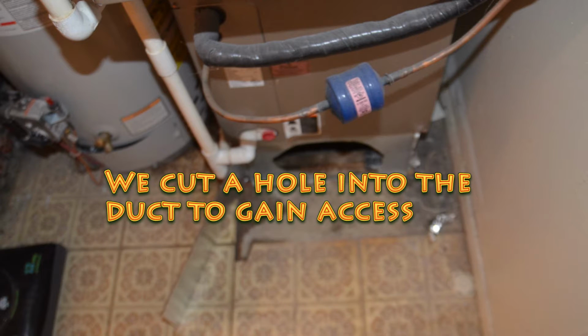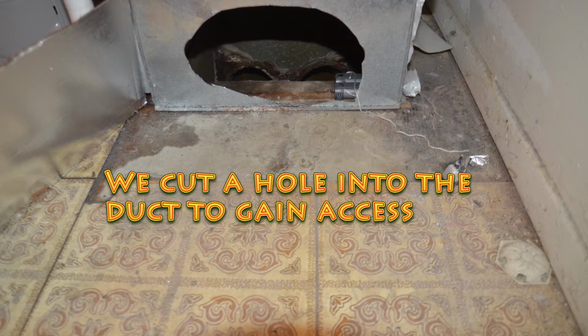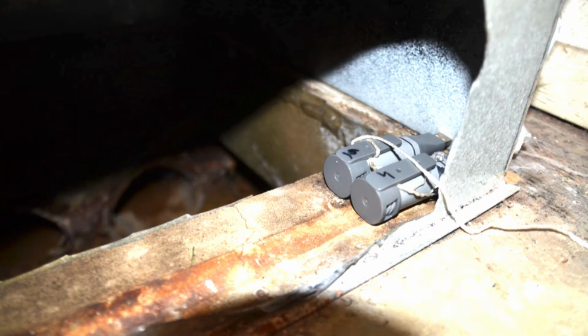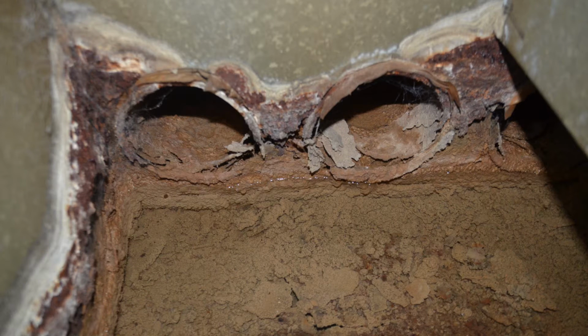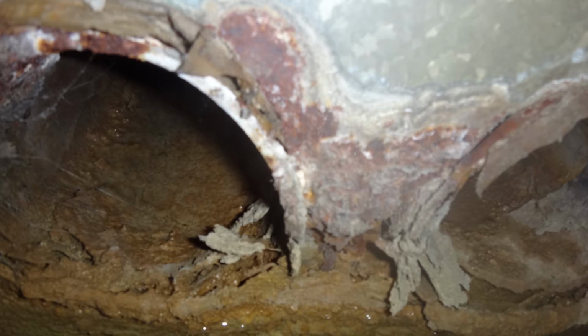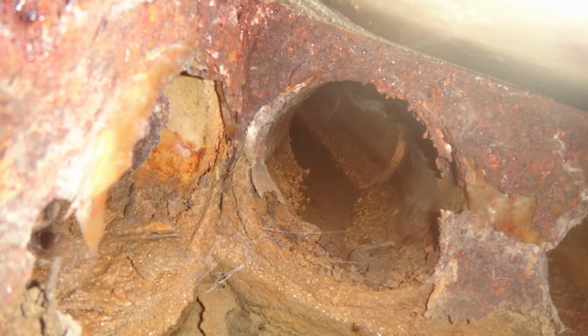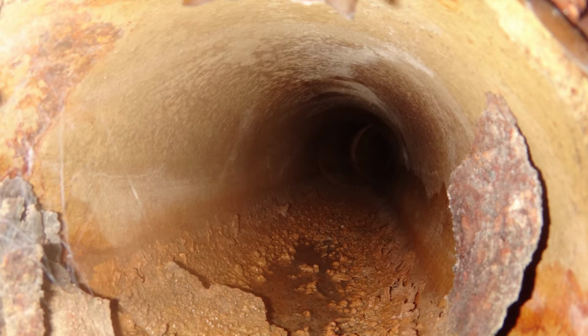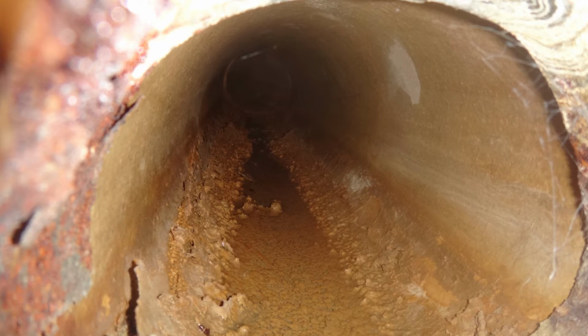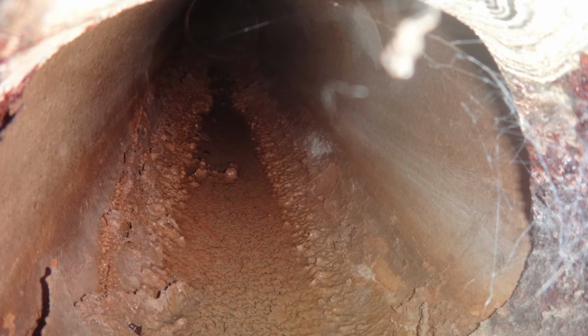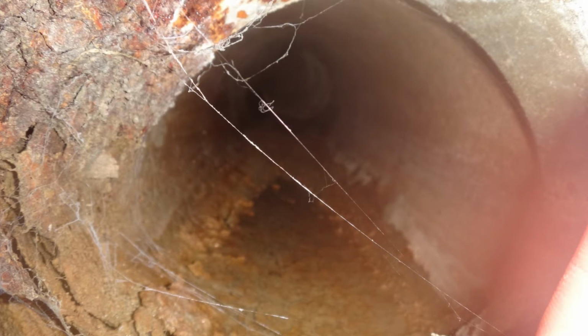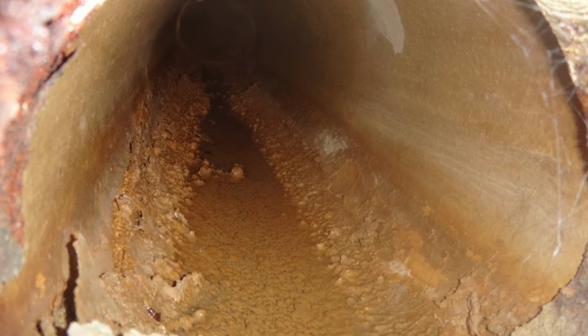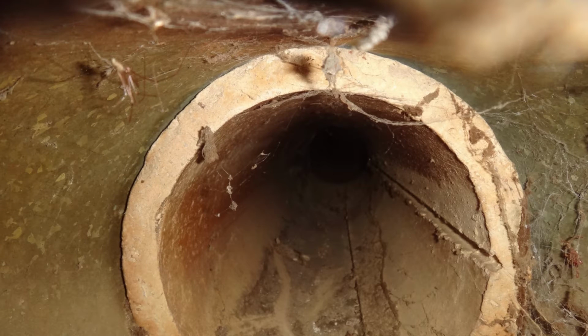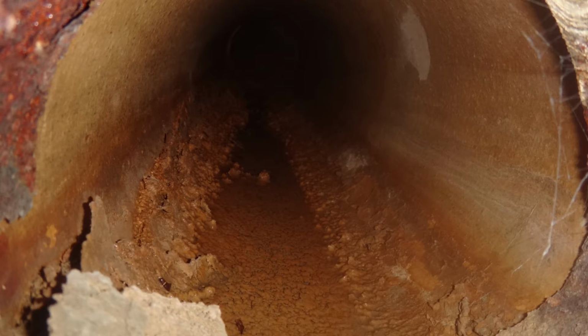We located the supply main HVAC trunk plenum duct. This main supply plenum duct traveled through the concrete floor and under the first floor concrete slab. It was connected to six other supply ducts that traveled under the concrete floor to all house rooms. The high water table, along with poor exterior water management, permitted water to enter the home's supply ductwork. The ducts were full of mold, bacteria, bio-sludge, bio-growth, and other pollution. Every time the HVAC system turned on, the home was contaminated with airborne bio-dust, mold spores, and airborne bacteria. Furthermore, the air had high humidity and was permitting mold growth on walls, ceilings, and cabinets.